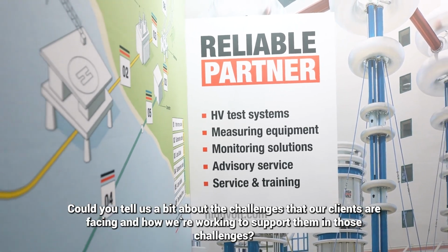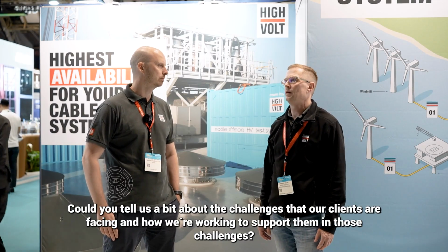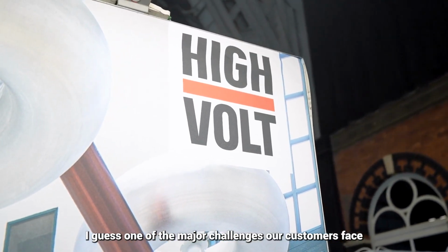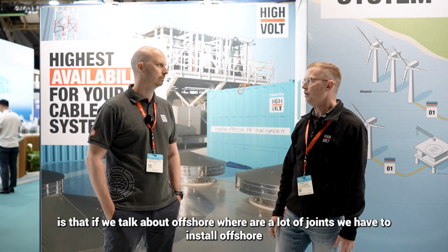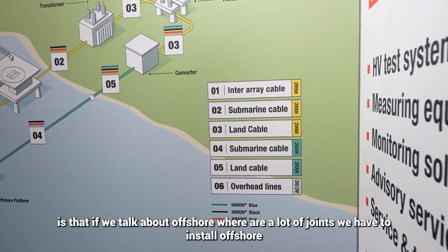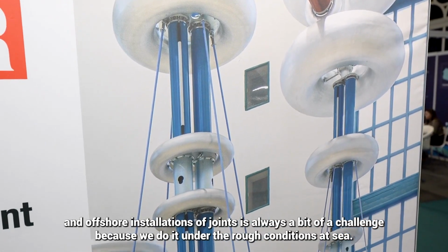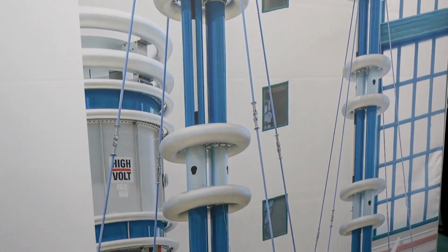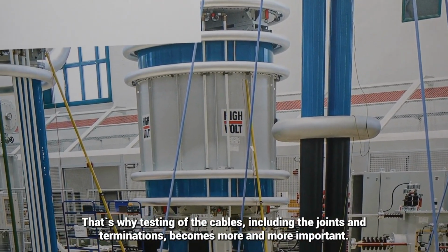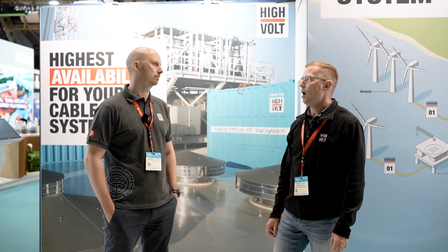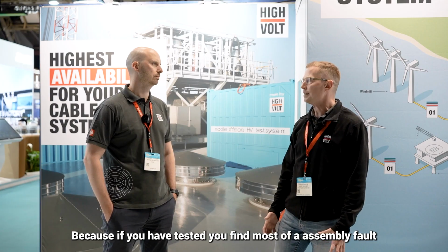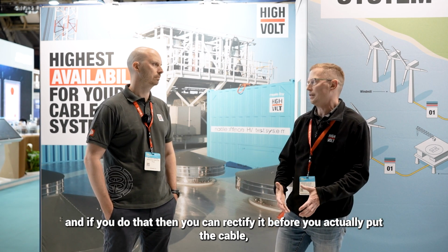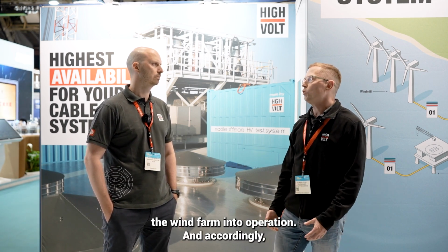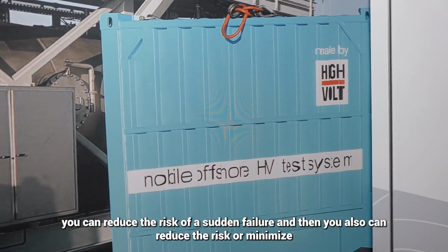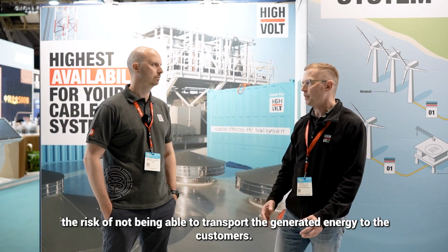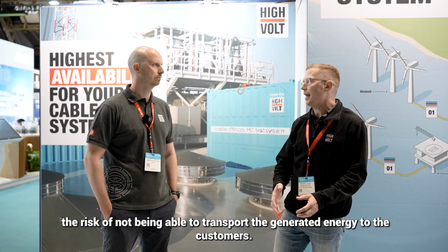Could you tell us a bit about the challenges that our clients are facing and how we're working to support them in those challenges? Yeah, I guess one of the major challenges our customers face is that if we talk about offshore, there's a lot of joints we have to install offshore, and offshore installation of joints is always a bit of a challenge because you do it under the rough conditions at sea. So that's why testing of the cables, including the joints and termination, becomes more and more important because if you have tested, you find most of the assembly faults, and if you do that, then you can rectify it before you actually put the cable, the wind farm into operation, and accordingly you can reduce the risk of a sudden failure, and then also you can minimize the risk of not being able to transport the generated energy to the customers.